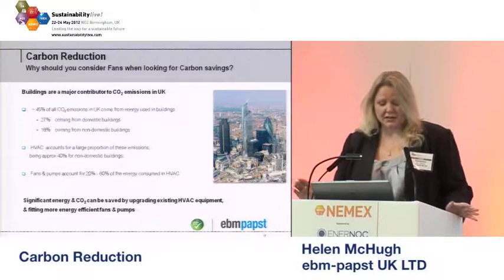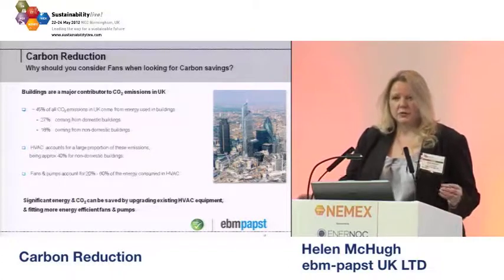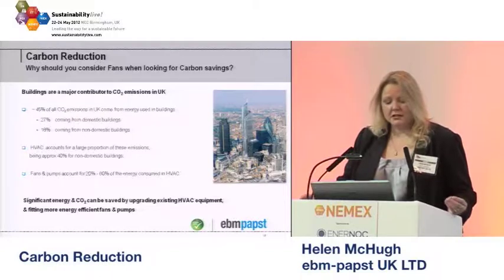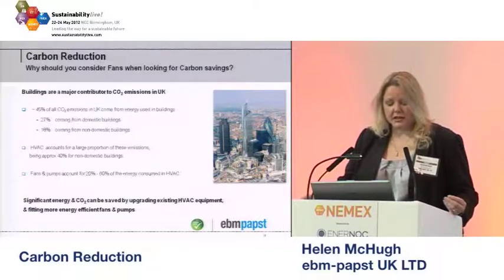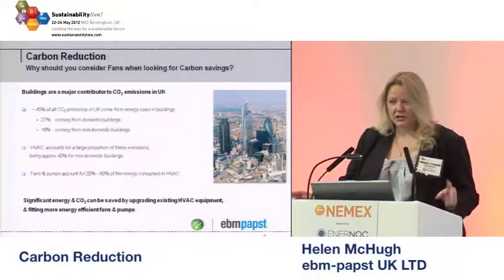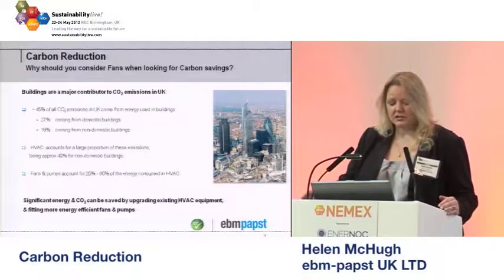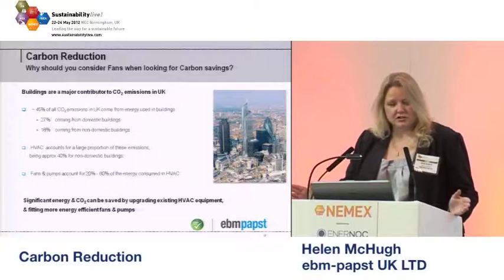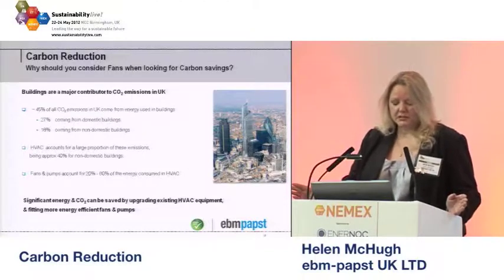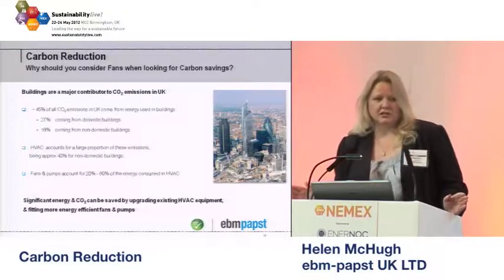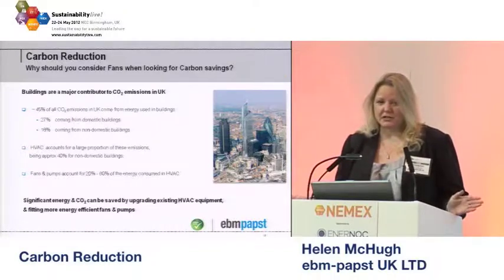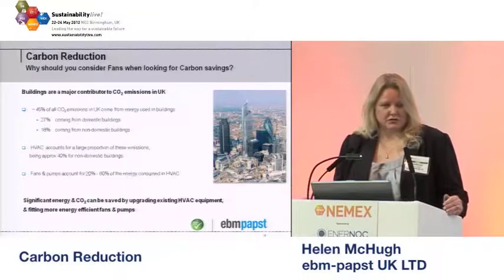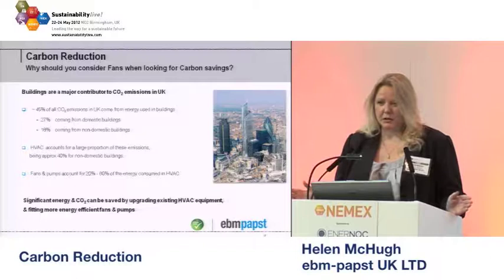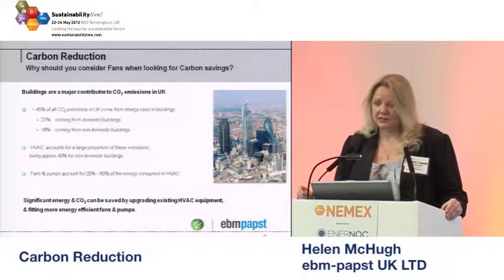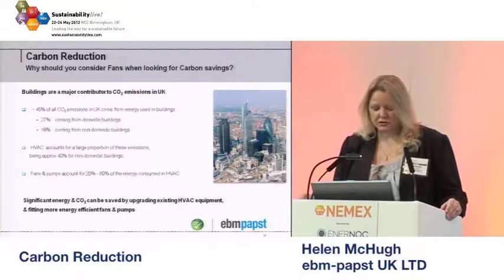So why is it important to consider fans when trying to reduce your carbon emissions? We all know buildings are one of the largest emitters of CO2 in the UK, both domestic and commercial. I'm going to concentrate specifically on commercial applications—on average, the HVAC equipment in your buildings will emit around 40% of all emissions in a commercial building. That will vary depending on the site, but it's the majority of your emissions. Within that, fans, pumps and motors can contribute between 20 and 60% of all the energy consumed. So it's obvious that fans and motors are a key factor when trying to reduce your emissions.